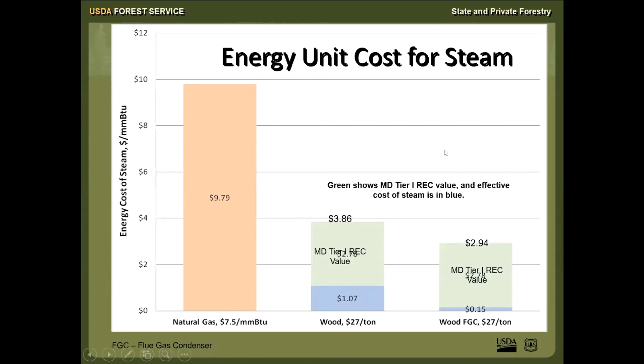you drive down the cost per unit of steam to $1.07 if you're not using flue gas condensation. But over to the far right, your energy unit cost for steam drops to 15 cents a million BTUs when you take advantage of that flue gas condensation and the improved efficiency of your system.